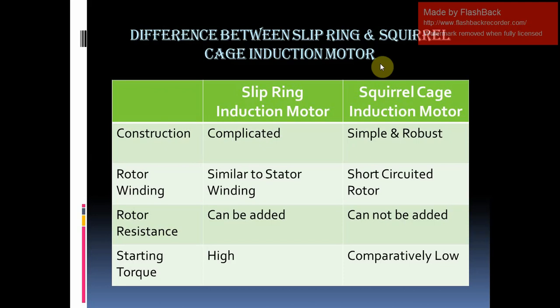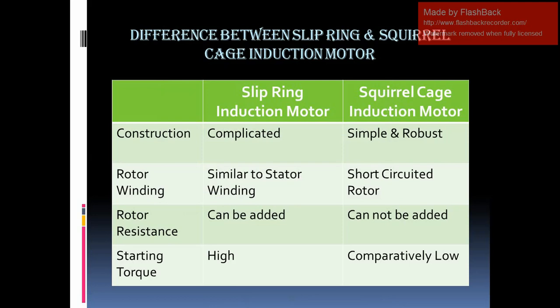Our next topic is starting torque. In case of slip ring induction motor, external resistance in the rotor circuit can be added to improve starting torque. While in case of squirrel cage induction motor, external rotor resistance cannot be added and the rotor resistance is very low, which is why the starting torque is comparatively very low.